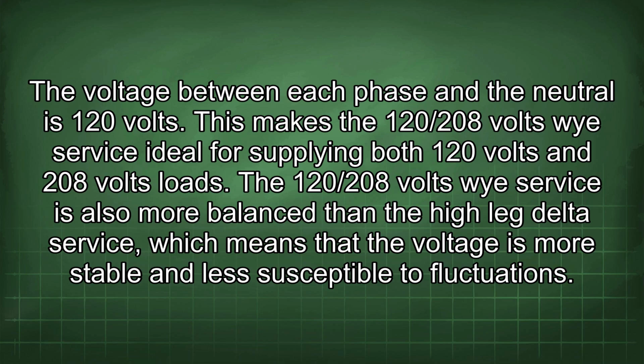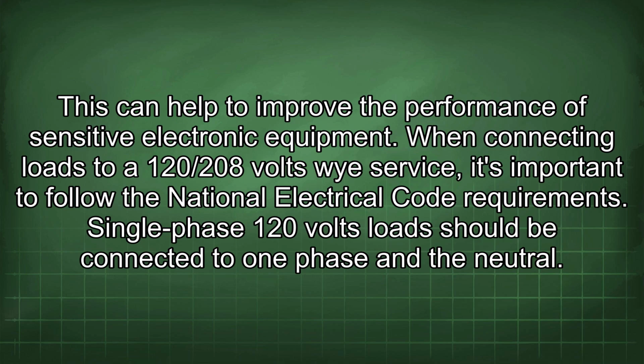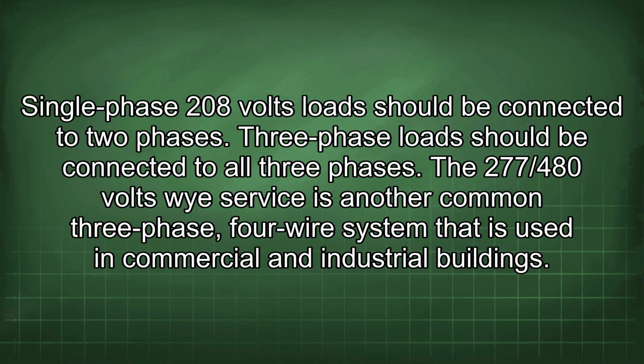The 120/208 volts Y service is also more balanced than the high leg delta service, which means that the voltage is more stable and less susceptible to fluctuations. This can help to improve the performance of sensitive electronic equipment. When connecting loads to a 120/208 volts Y service, it's important to follow the National Electrical Code requirements. Single-phase 120 volts loads should be connected to one phase and the neutral. Single-phase 208 volts loads should be connected to two phases.